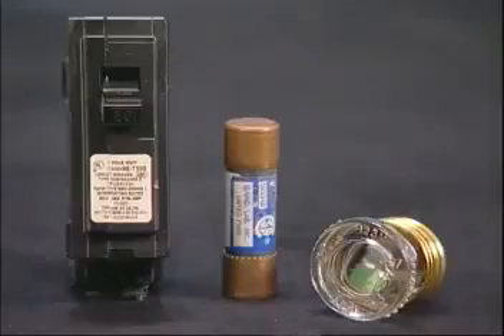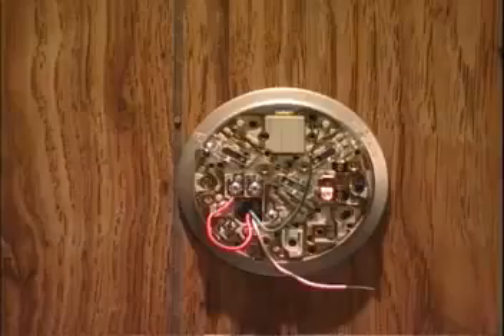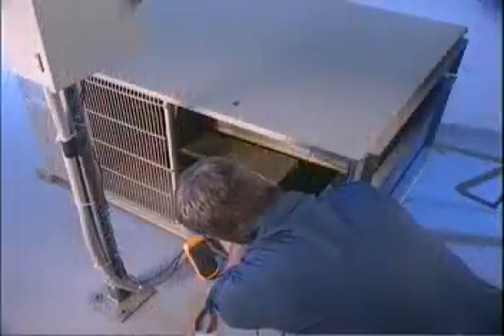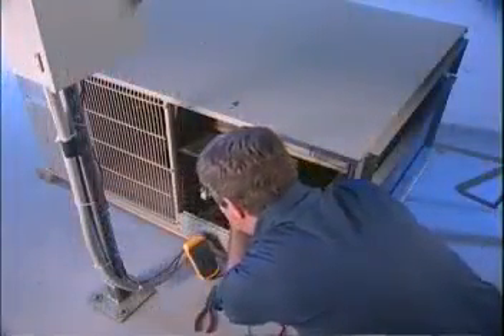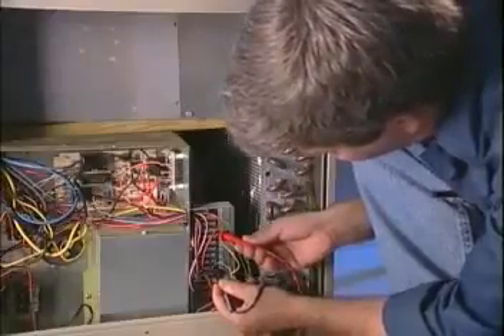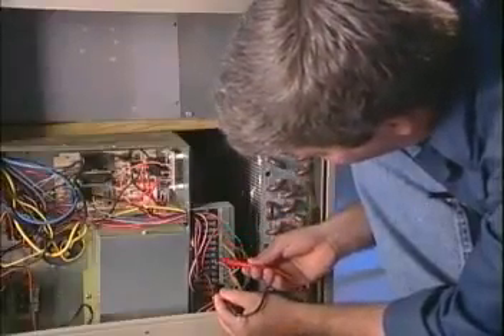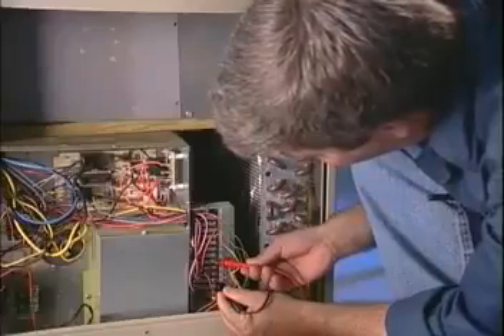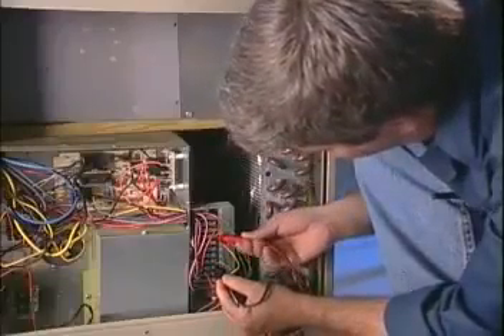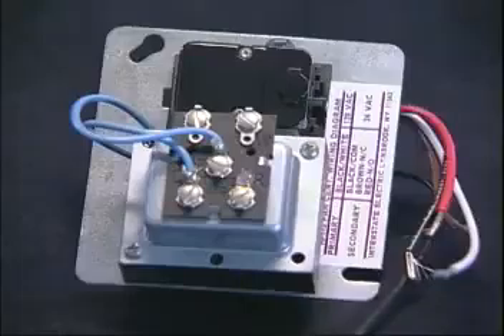Control wiring, on the other hand, does not supply line voltage to the motors and system devices, but it does signal these components when to cycle on and off. For this reason, control wiring is just as important as power wiring. Control systems used in residential application are almost always of the low voltage variety, utilizing a control transformer to provide the 24-volt power supply for the control circuit. The transformer is often located in a fan relay package located within the air handler or furnace.